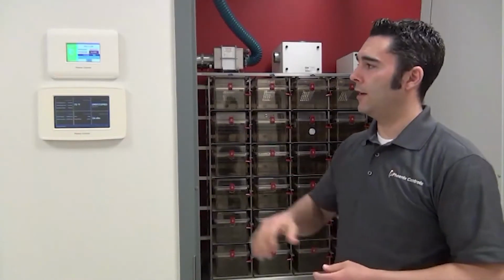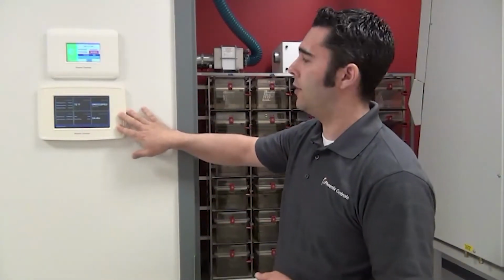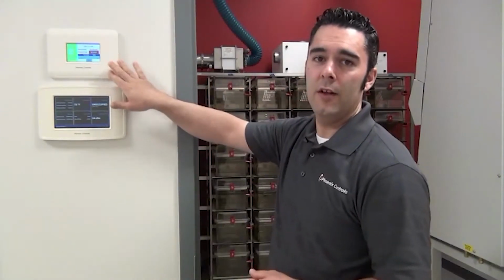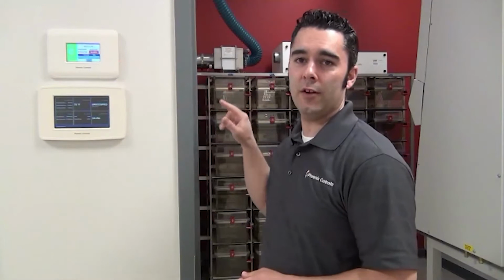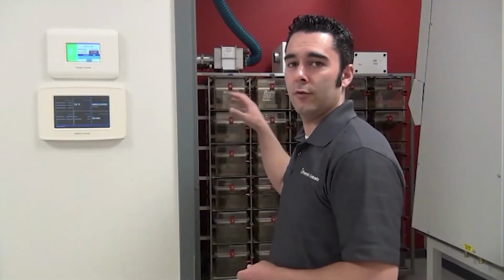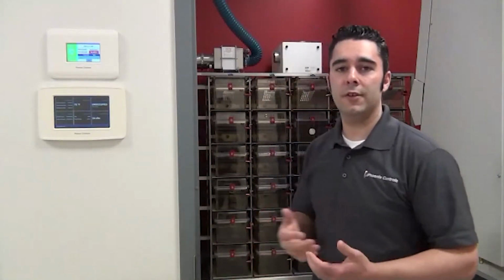In addition to the cage rack that we have in here and the biosafety cabinet, if you notice here on the wall we have a Phoenix Controls view. Above that we have an advanced pressure monitor. This has a pressure transducer built into it that's monitoring the differential pressure between the corridor outside the room and the pressure inside the room. Now traditionally when you're doing offset inside of a wet chemistry lab or non-critical or not as critical applications, you just have a fixed volumetric offset. So for wet chemistry labs you might have a -150 or a -200 CFM. Sometimes there's a rule of thumb that 10% of your total exhaust is a good starting point for your offset. Some people mandate 150 CFM or 100 CFM per door opening going in there.